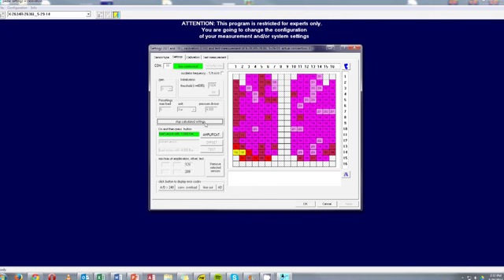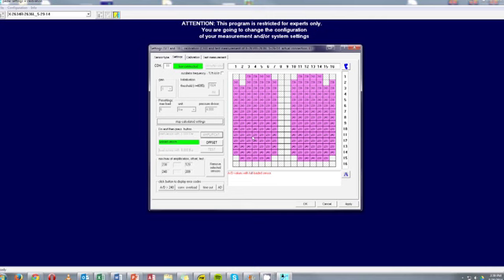The software will ask you to load the insoles to 6 bar. Since we are performing an amplification step, you will want to go above 6 bar to about 6.1 or 6.15 bar. After loading the insoles in the calibration device to the desired pressure, click the amplification button. You can now see that these are the A to D values with the fully loaded sensor.